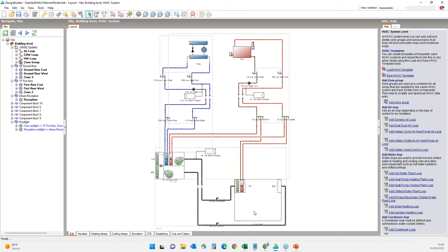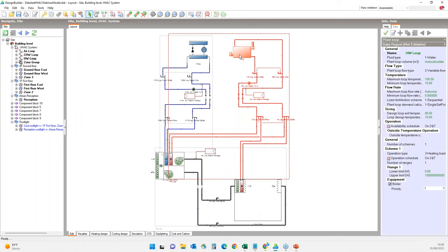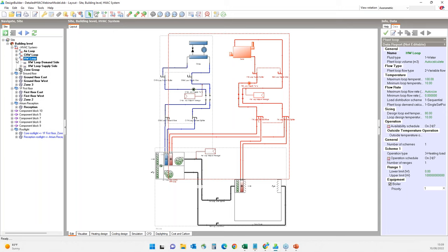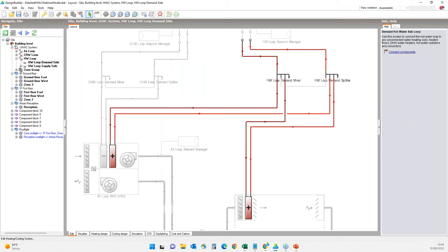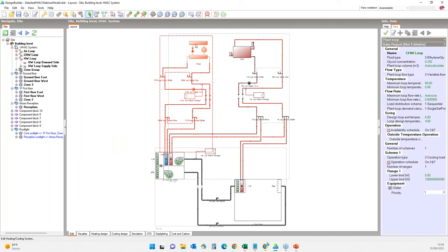As we are using a template system, it uses EnergyPlus default settings, so in this part of the webinar we will try to improve these defaults for more optimal performance. Hot water loops provide hot water to heating coils in the zone and in the air handling unit. The hot water loop is made of two sub-loops: the supply side sub-loop which contains all the plant equipment, and the demand sub-loop for connections to the zone level equipment.